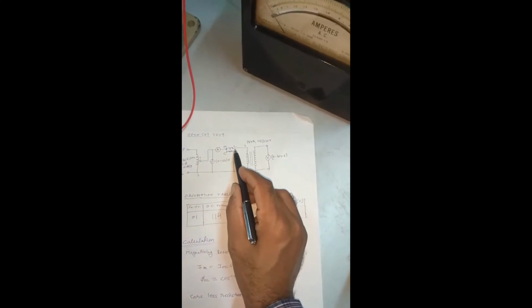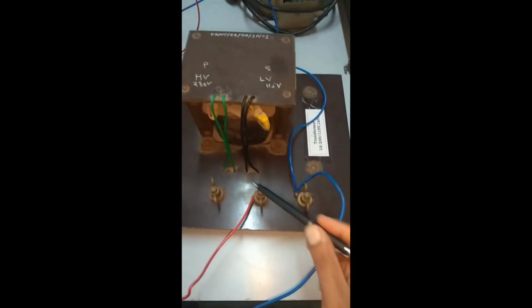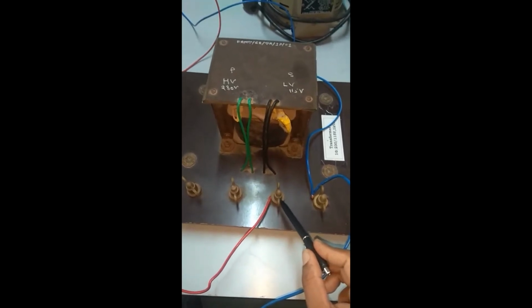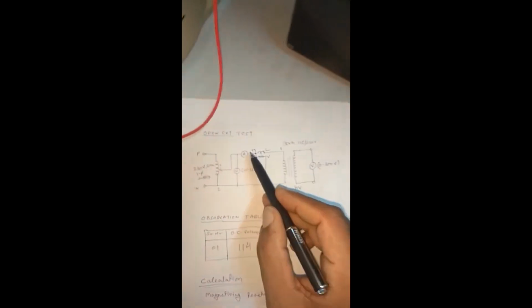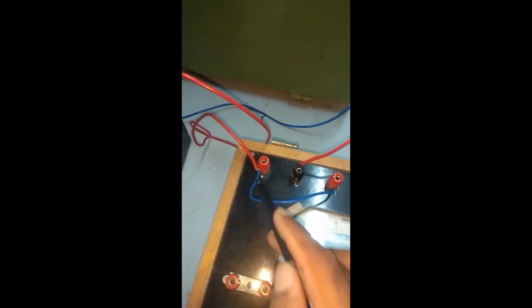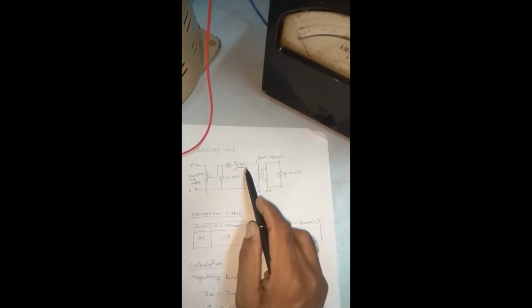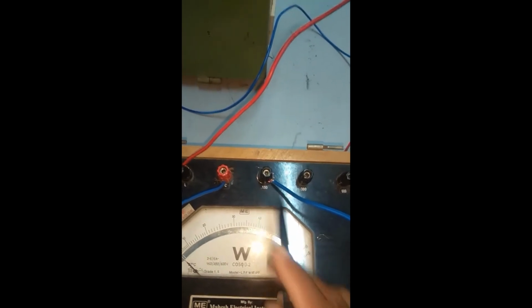So we have connected one wire from the ammeter to the main terminal of the wattmeter. Then L is connected to the first terminal of the LV of the transformer. Here is the L, and we have connected one wire here, which has to be connected to the first terminal of LV. Here are the two terminals which are brought out, so we are connecting to this terminal. Just see the connection: we have shorted M and C with one connecting wire. In the other connection, V is connected to the second terminal of LV. Here is the V. We are going to use the 150 volt range. One wire is connected over here, and the other terminal of LV, the second terminal, is this one.